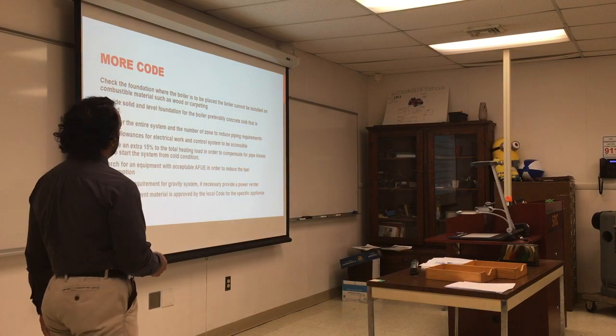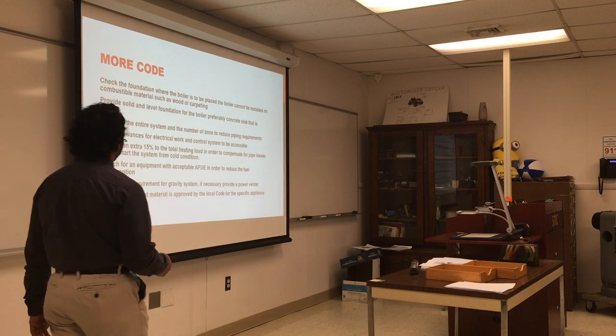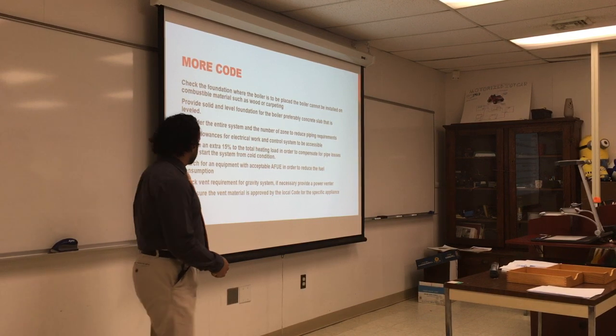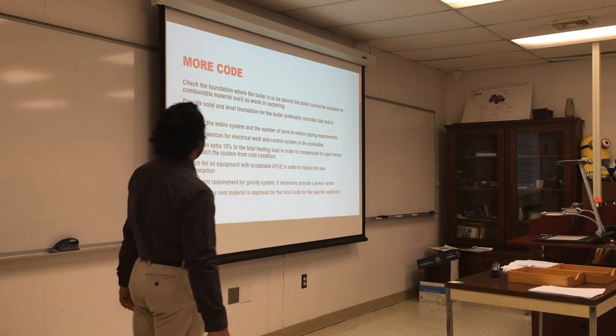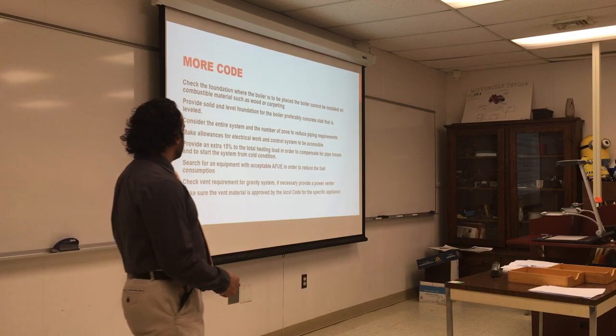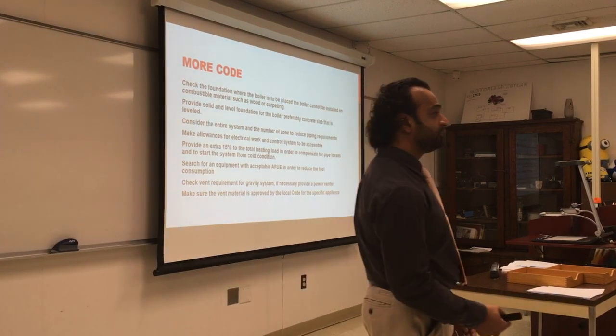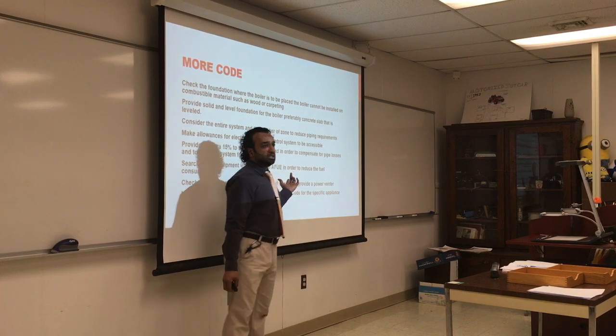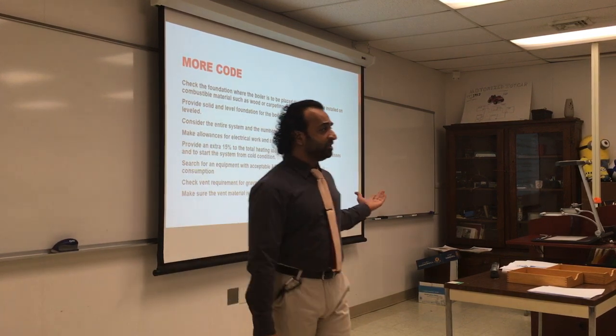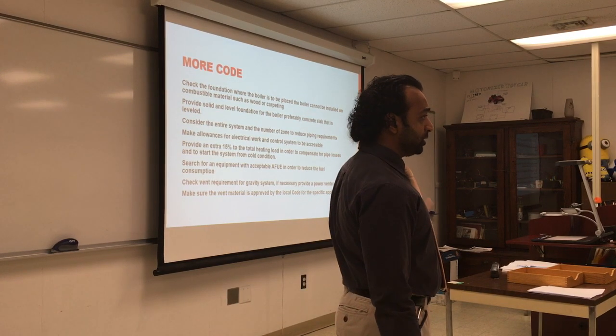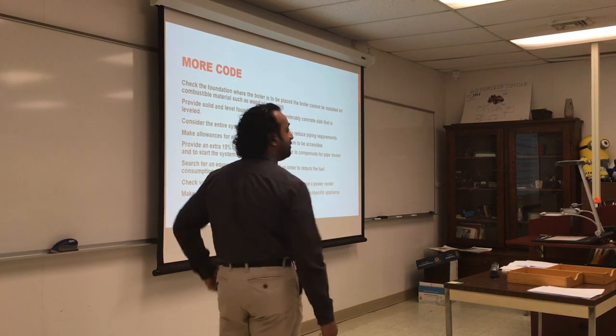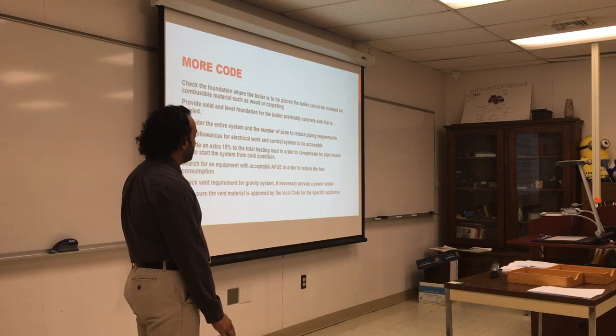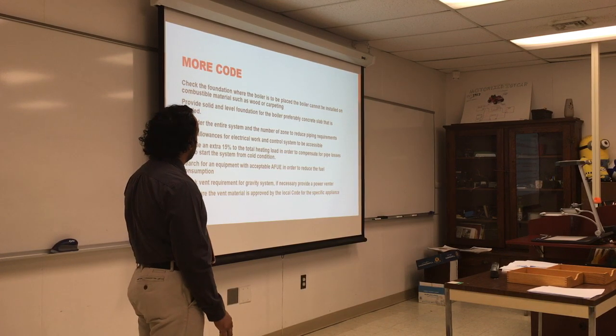Provide 15% for the total heating load in order to compensate for pipe losses and cold start. When you shop for equipment, make sure it has acceptable fuel usage efficiency — that means better combustion efficiency and better thermal efficiency. For now, condensing boilers are very common, especially where you have gas, and it's really good to have something with higher efficiency.